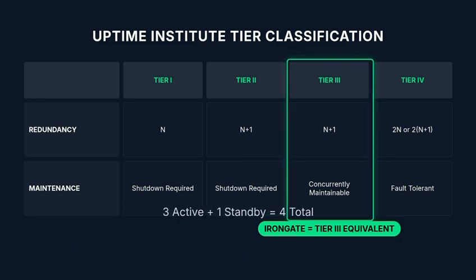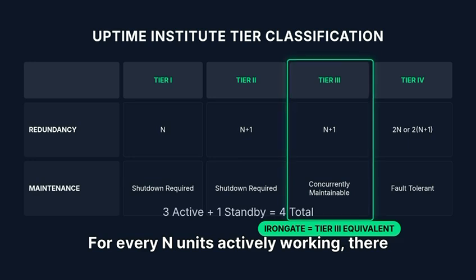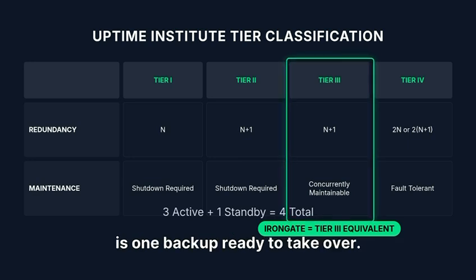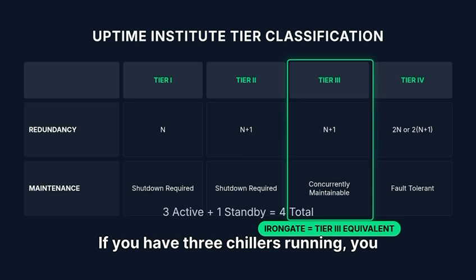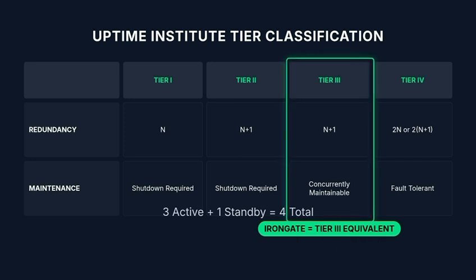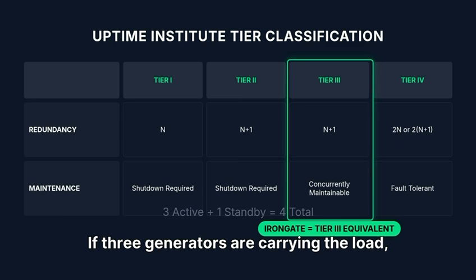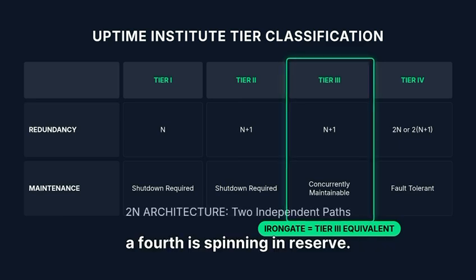The baseline resilience architecture is N+1. For every N units actively working, there is 1 backup ready to take over. If you have 3 chillers running, you have a 4th on standby. If 3 generators are carrying the load, a 4th is spinning in reserve.